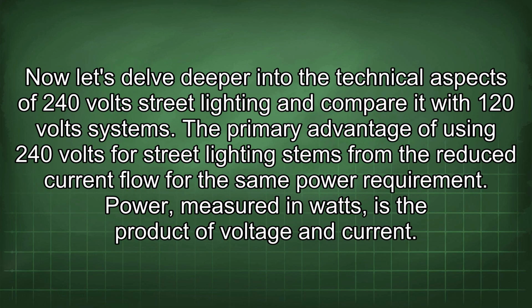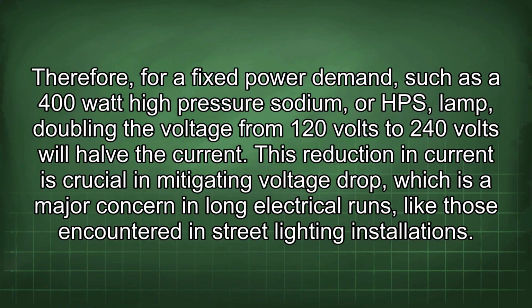Now let's delve deeper into the technical aspects of 240 volt street lighting and compare it with 120 volt systems. The primary advantage of using 240 volts for street lighting stems from the reduced current flow for the same power requirement. Power, measured in watts, is the product of voltage and current. Therefore, for a fixed power demand, such as a 400-watt high-pressure sodium or HPS lamp, doubling the voltage from 120 volts to 240 volts will halve the current.